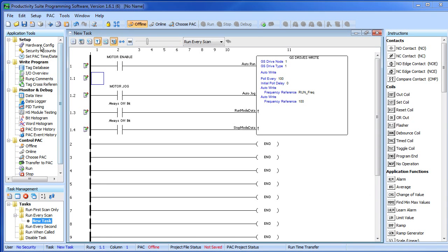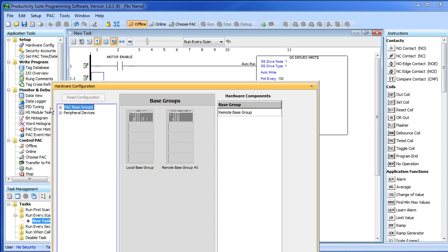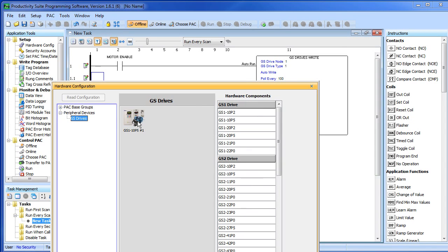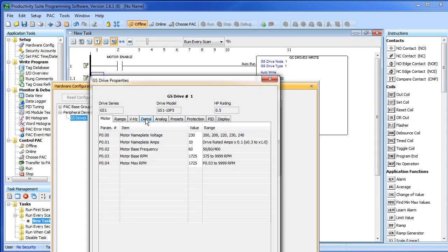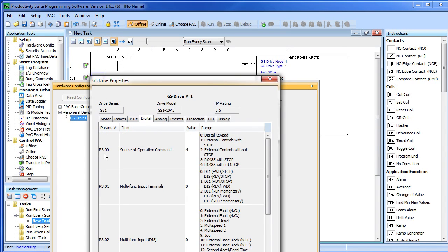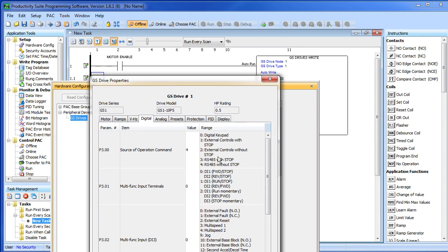Just go up here to the hardware configuration, select the VFD and go to the digital tab. Parameter 3.00 selects the source of control. A 0 says use the keypad that is on the drive. 1 and 2 say use the external inputs on the drive which you can control with manual switches or even digital I/O from the controller if you want to.